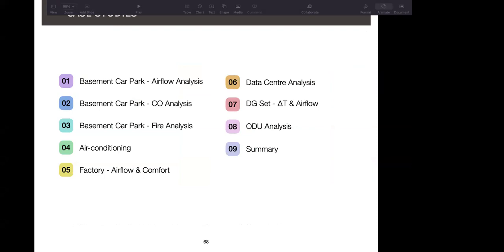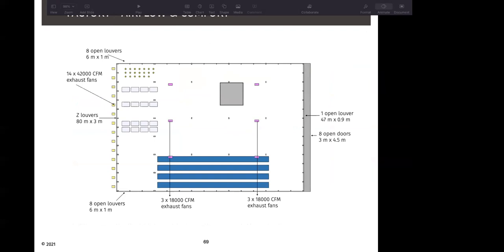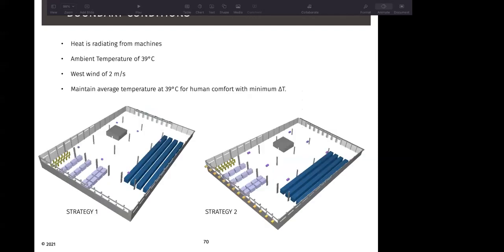The fifth example is for a factory, airflow and comfort. Again, for a factory area, there are multiple equipment which are radiating heat. There are exhaust fans provided on one side with openings provided on the other 3 sides. And then there are some jet fans provided at the center to propel air from one end to the other. Again, we are looking at 2 strategies. The purple and the green shown within the factory space are the equipment which are radiating heat. The blue is the racks, and then there is a plant room which is shown in gray.